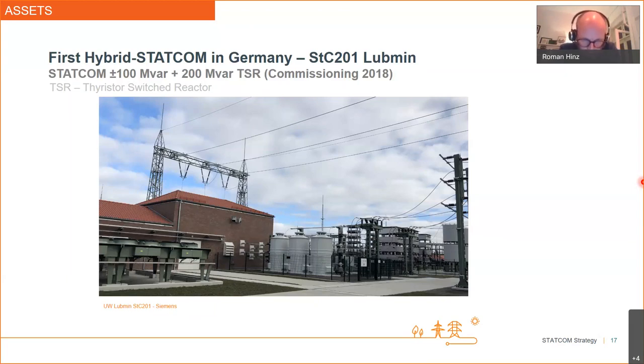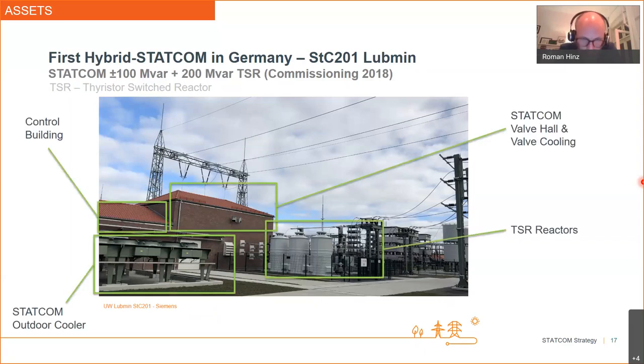And yes, you can maybe also go a little bit further, Cornelius, because you have made a picture of this STATCOM. Here you see the building, also the outdoor coolers and the TSR, the thyristor switched reactor, and in here also the building with the converter, the cooling, so that you have an impression how those kind of STATCOMs look like and how big they are. As you see here, this is a 100 MVA STATCOM. What we are looking for in the future is a 300 MVA STATCOM, which for sure will be larger than this installed one. So for us in asset management, it was a little bit tricky in this short term to specify those kind of new STATCOMs. And also you have seen that we want to install several of them. So can you please go to the next slide?